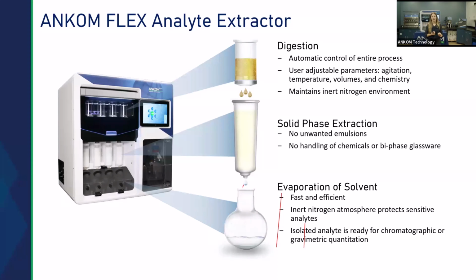The center section here, where you can see the solid phase extraction column pulled out, is the extraction section. So this is where you can eliminate unwanted emulsions. You don't need to handle chemicals and biphase glassware. And this is where your extraction step would take place. Then the bottom portion of this instrument is our evaporation chamber, is what we call it. This is where the evaporation of your solvent takes place under low heat and a nitrogen input. Everything, again, throughout the whole system is under nitrogen, so it keeps your analyte protected.